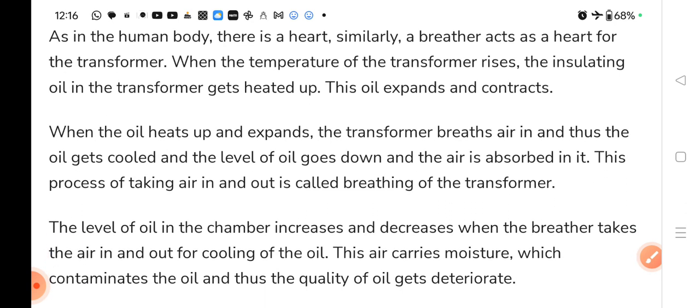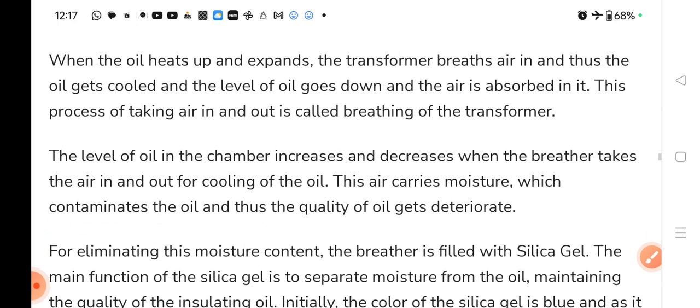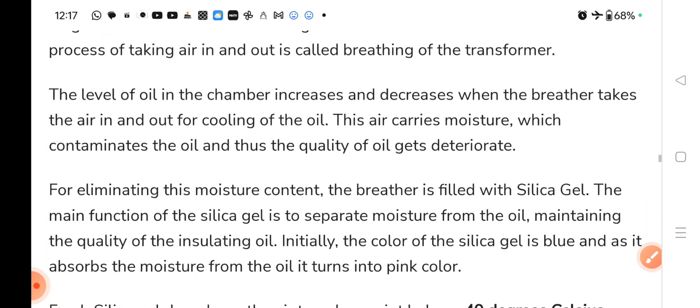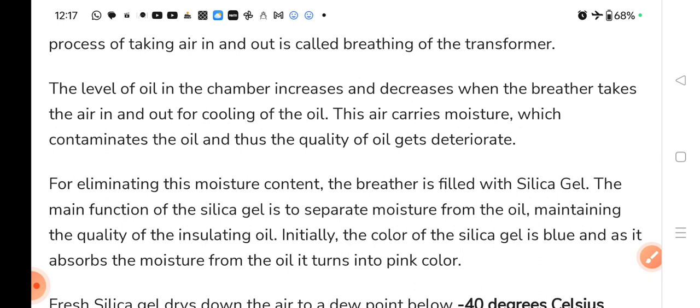The level of oil in the chamber increases and decreases when the breather takes the air in and out for the cooling of the oil. This air carries moisture which contaminates the oil and the quality of oil gets deteriorated. जब breather air in करता है तो air में moisture के होने की वजह से हमारा oil contaminate हो जाता है और quality भी deteriorate हो जाती है. For eliminating this moisture content, the breather is filled with silica gel — तो हम silica gel रखते हैं उसमें.